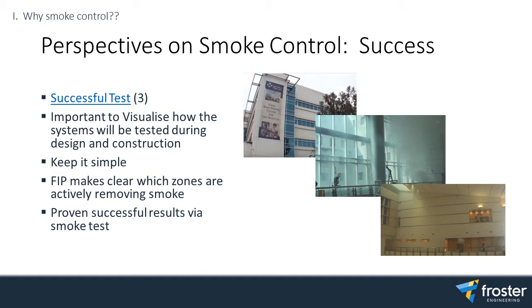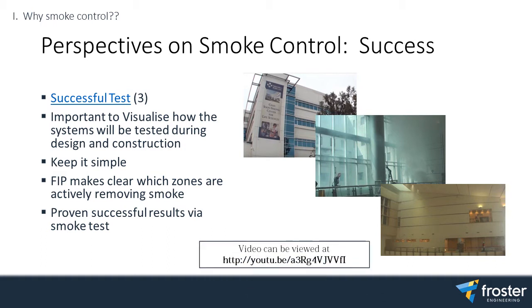So in the atrium, they're setting up a smoke test. So this is commissioning for the building. They're just ensuring that the fire control systems work. The FIP is showing them the zones which need to extract, ensuring the fans are doing their job, and confirming how quickly they can evacuate the zone. You can see from a few of the slides here, that's just showing actuated dampers opening and closing, fire curtains closing, fans operating. This cleared out, and there's the print screen of the FIP, the building control system. It cleared in about 10 minutes.